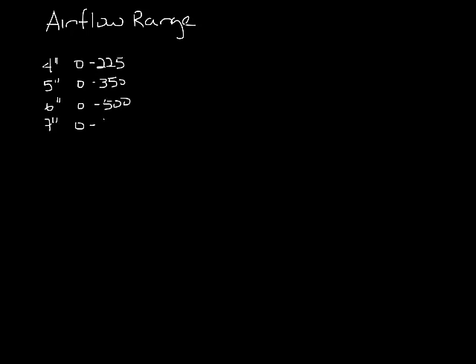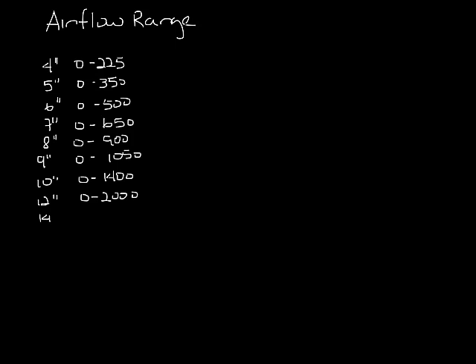Our catalog shows the airflow range for different inlet sizes. So for a 4-inch inlet, the inlet CFM is shown as 0 to 225 CFM. For a 5-inch, 0 to 350, 6-inch, 0 to 500, 7, 0 to 650, 8, 0 to 900, 9-inch, 0 to 1050, 10-inch, 0 to 1400, 12-inch, 0 to 2000, 14-inch, 0 to 3000, and 16-inch, 0 to 4000.